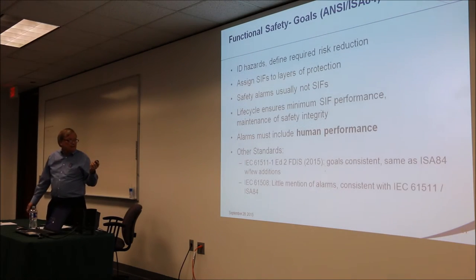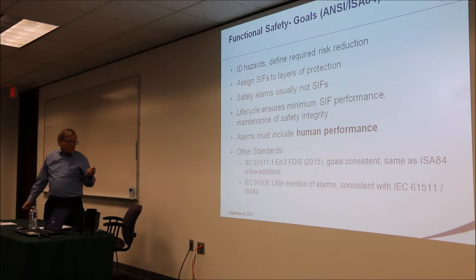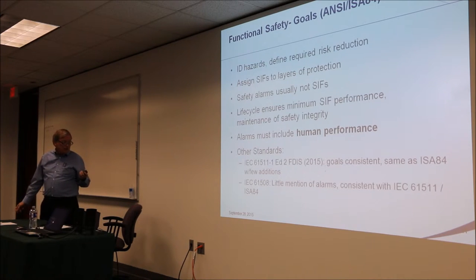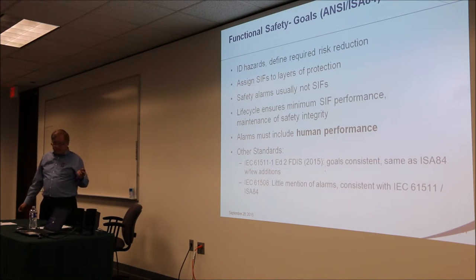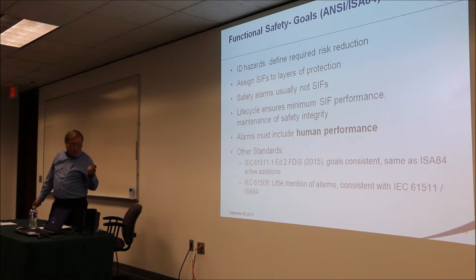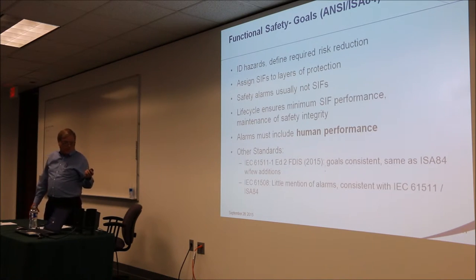Moving to ISA 84 at a high level: you want to identify the hazards, identify your SIFs, and assign them to protection layers. Safety alarms generally are not SIFs because generally people don't take higher than a 10-to-1 risk reduction, though we'll talk about cases where folks do. The life cycle is aimed at ensuring those SIFs perform as needed to maintain safety integrity. Other standards, IEC 61511 and 61508, don't have much in the way of differences from 84.